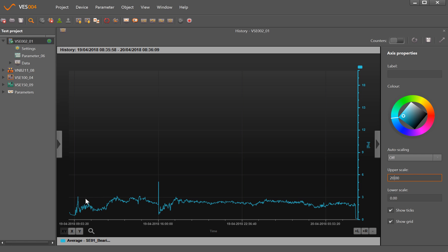So you can see from the start of the history trend there's not been a great deal of change. I mean this is milli g's, so this isn't real life values you would normally get out in industry, but it's still a trend nonetheless. And you can see that for most of the time it settles around about 2 milli g's, and we have alarm limits set at 450 and higher than that for the red. So if this was a real machine and those were where the limit levels were, I'd be looking to change those levels.